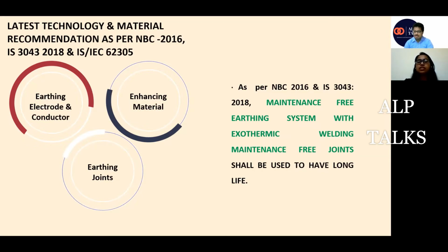Sure. Basically, initially, as maybe you know, for earthing, people were using salt and charcoal. Yes, that's true. The conventional types of earthing, right? Yeah. But now our latest standards are recommending maintenance-free earthing. And they have prohibited the use of coke, grease, and salt and charcoal. The National Building Code was revised in 2016. It has strictly recommended that we should not use salt and charcoal, as it increases the corrosion in our earthing system, and it also degrades the conductor. The salt is conductive, but it degrades the material with which we are using it.